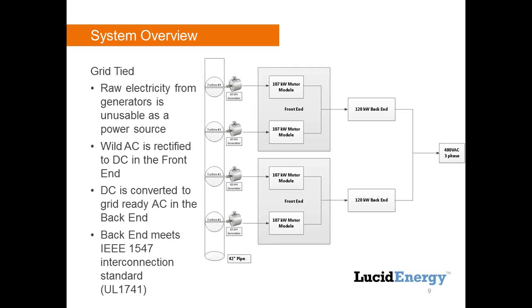We run it underneath the street up to a power pole, up to transformers that step it up to whatever transmission voltage they have at that site. Going from AC to DC to AC adds one level of complexity, but it's straightforward and simple. We don't have to run the turbines at a fixed speed — we let them run at any speed the water happens to be pushing them. That makes it a lot easier to optimize the turbine, allowing the generators and turbines to run in their peak efficiency modes no matter what the water flow is, giving us flexibility to operate across a wide range of flows and pressures.